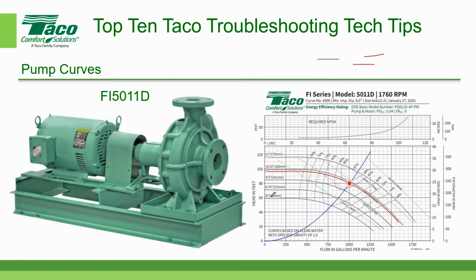Okay. So what I'm going to do is take the field data that they gave me, and they said they measured a pressure differential of 92 feet. So if you'll notice, this line here is 80 feet, there's 80, and there's 100.